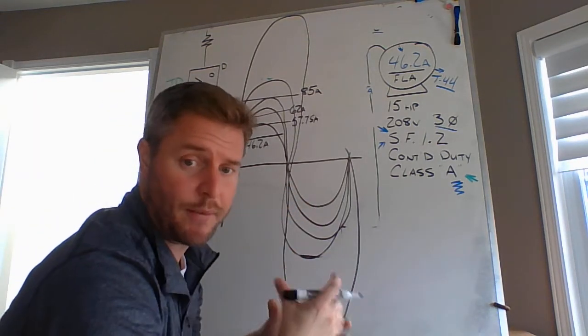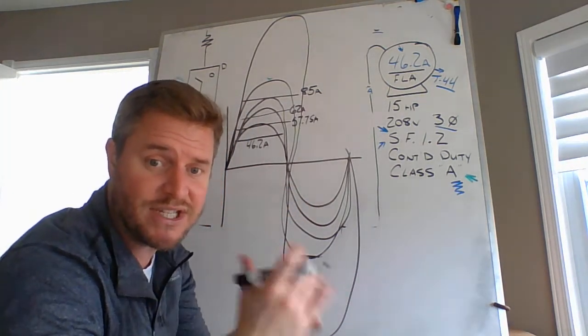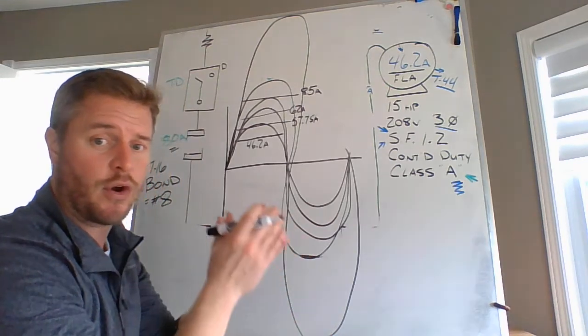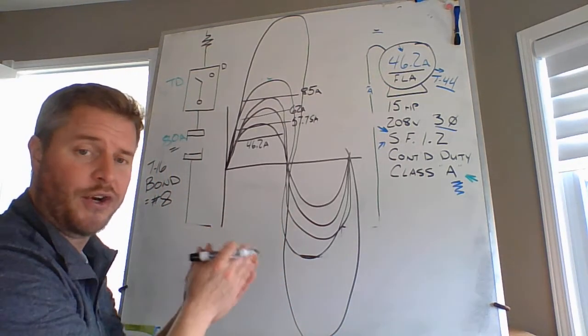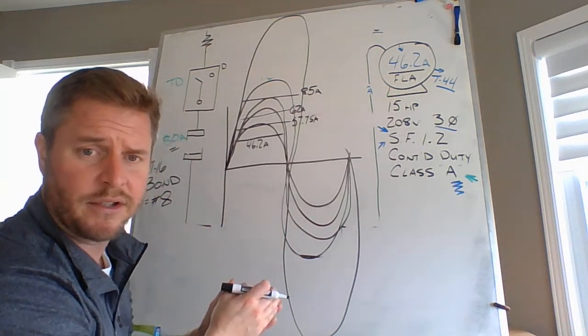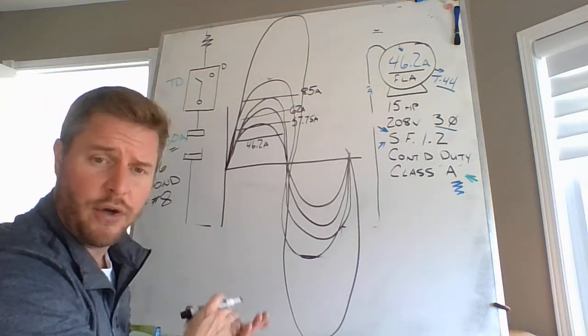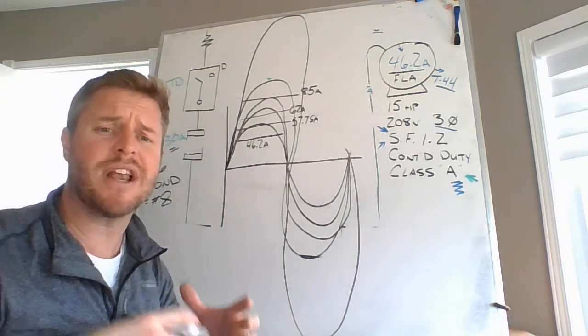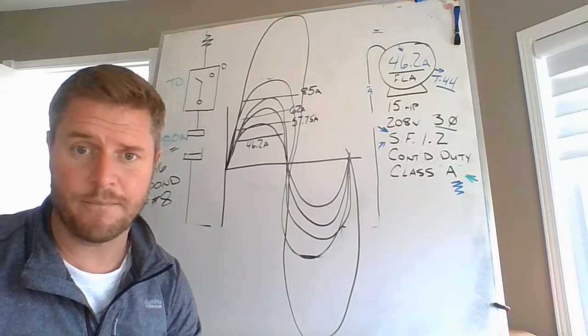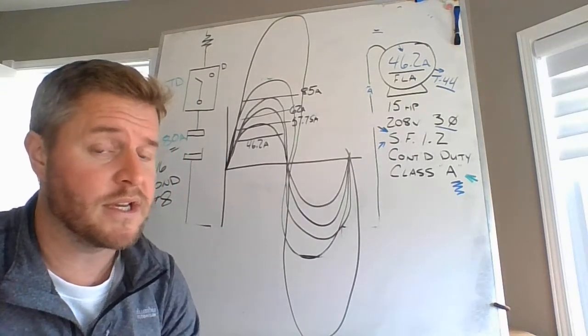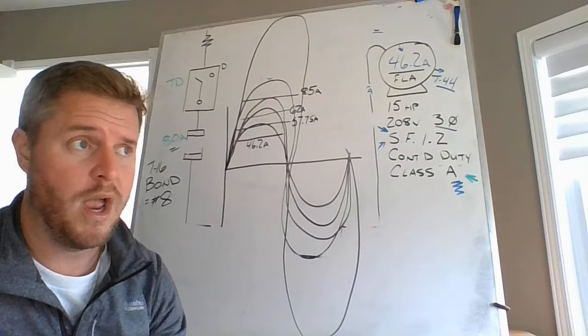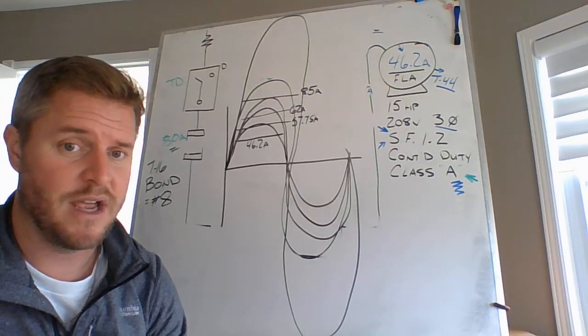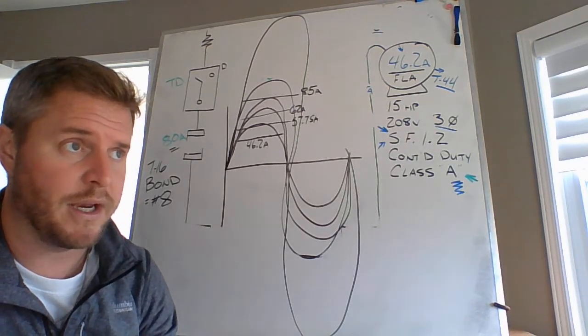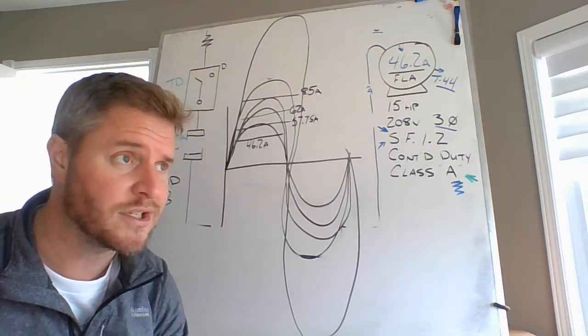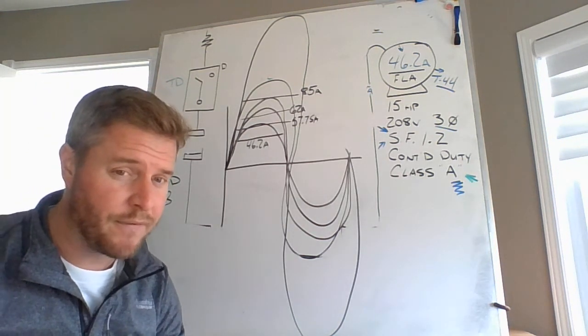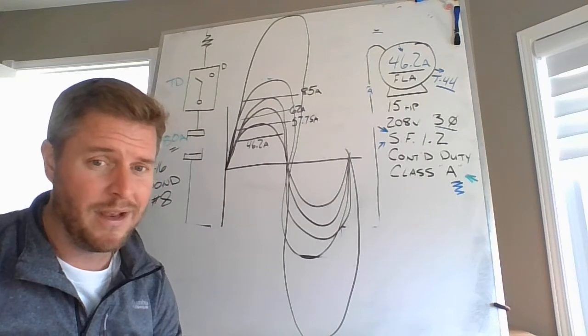There's a mistake. There's something wrong with that motor. You've got a dead short. That means that you're going right from a current carrying conductor right to your bonding conductor, which is directly connected to your grounding conductor, which means there is no resistance in that circuit. And if there is no resistance in that circuit except for internal wire resistances, like say, the values that we calculated for voltage drop calculations, that's a very, very, very small value.